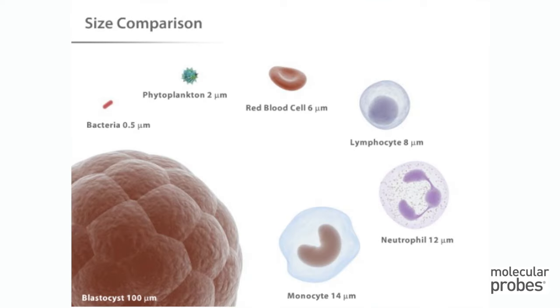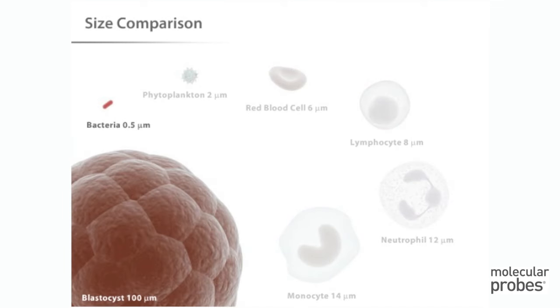In fact, flow cytometers can accommodate cells that span roughly three orders of magnitude in size. In most cases, cytometers will be detecting cells between 1 and 15 microns in diameter, although through the use of specialized systems, it is possible to detect particles outside this range. Now let's see how laser light is used to detect individual cells in the stream.